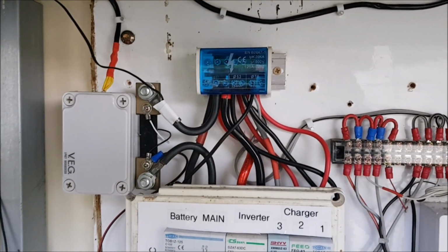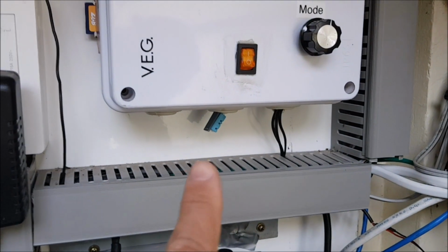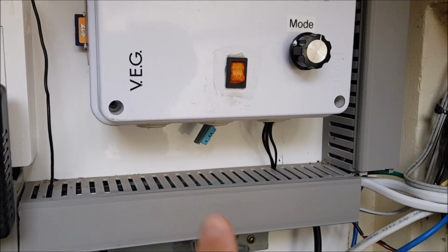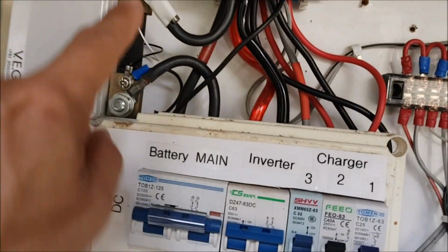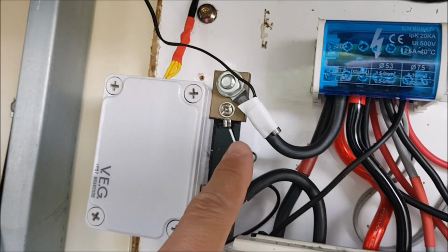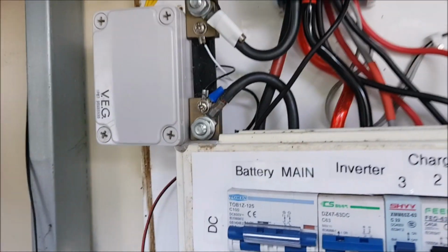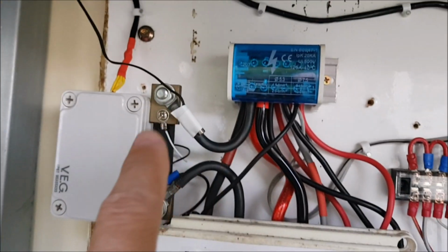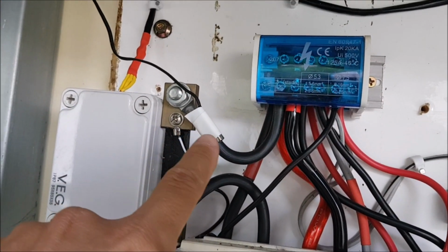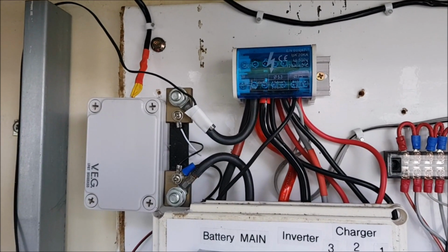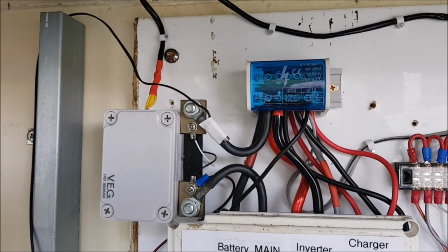Then we have our temperature sensors - actually 4 total. This is the main temperature and humidity sensor of the controller, but then I have 3 thermistors like this one, which were before somewhere on the cells, completely useless. One will come here at the shunt - this is the hottest place in the system. I'm measuring up to 63 degrees Celsius there.